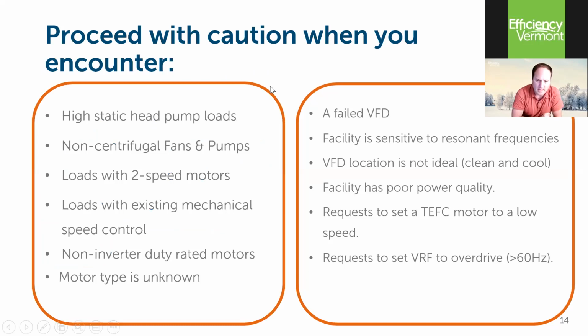So as much as I'd love to get drives on everything, it's not practical, and there are some caution signs to look out for when you're out there looking at VFD opportunities. So high static head pump loads, this is some water systems, non-centrifugal pumps and fans, so positive displacement pumps, for example, not a great application for a VFD.